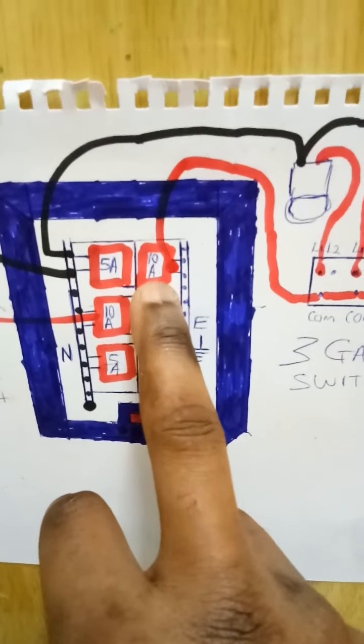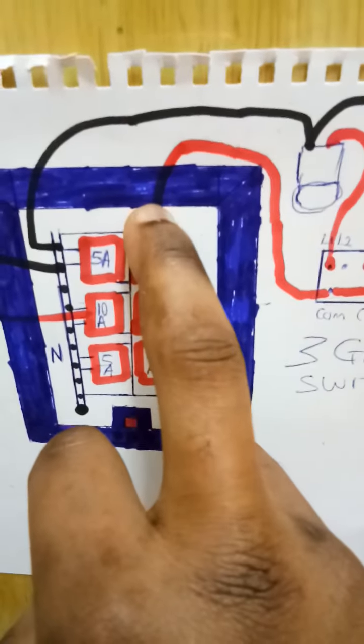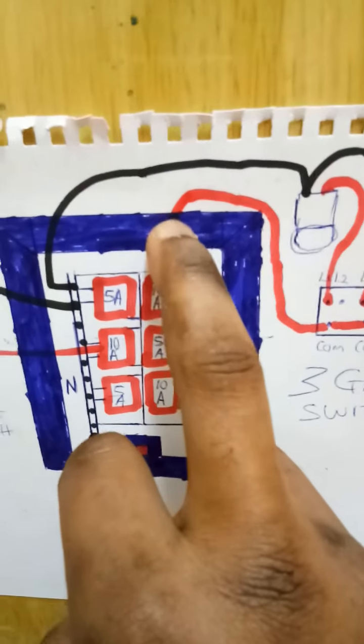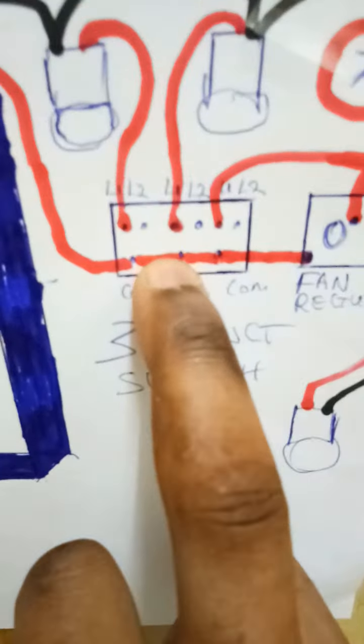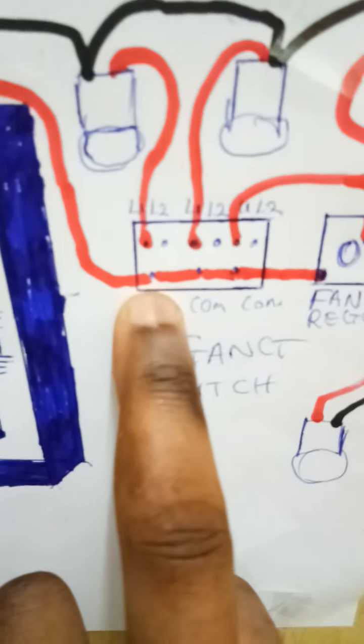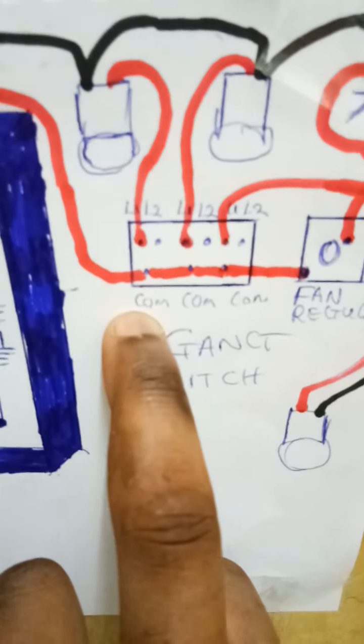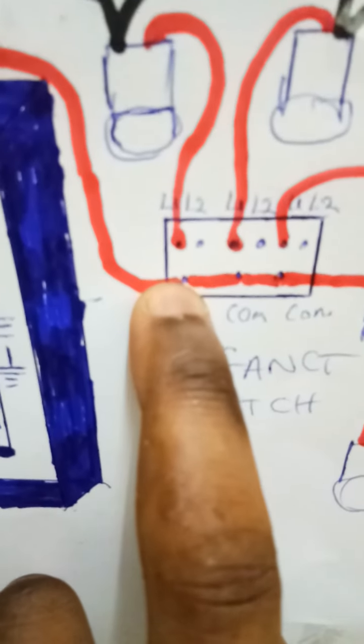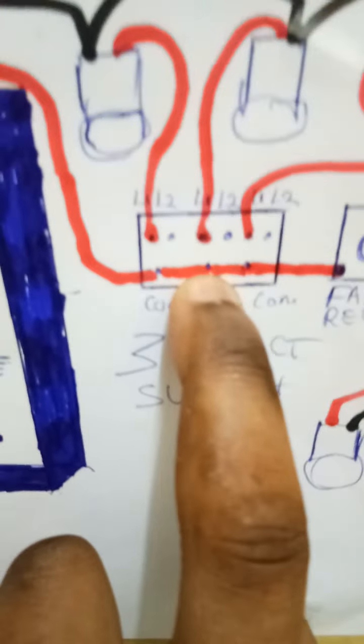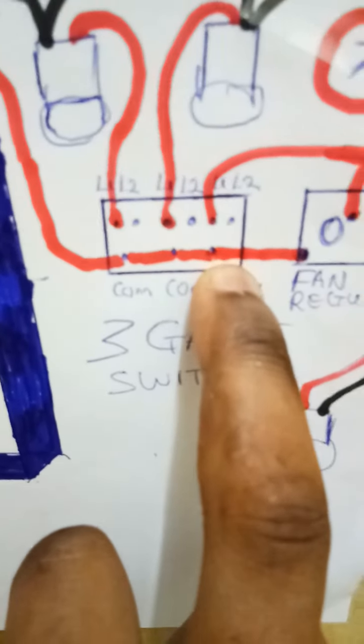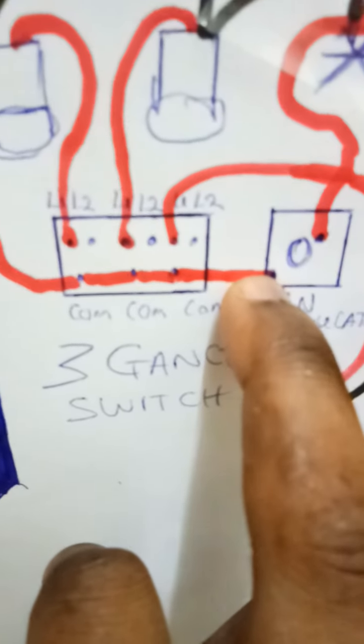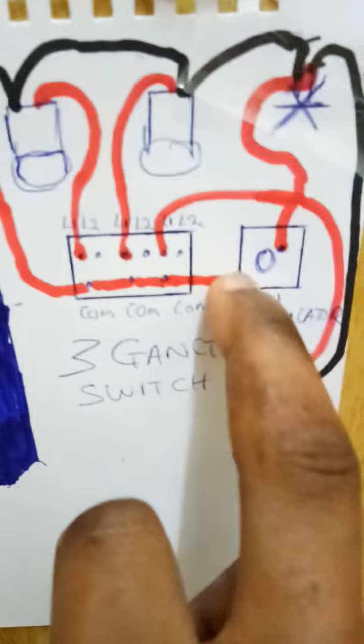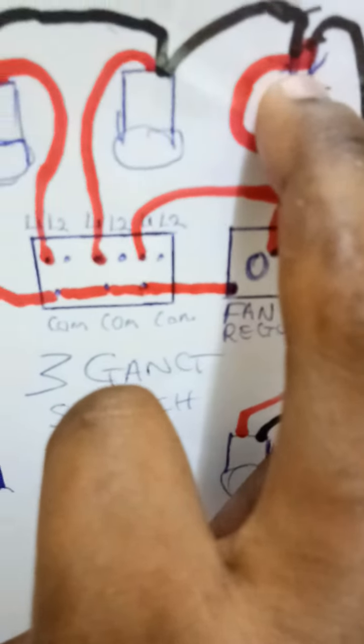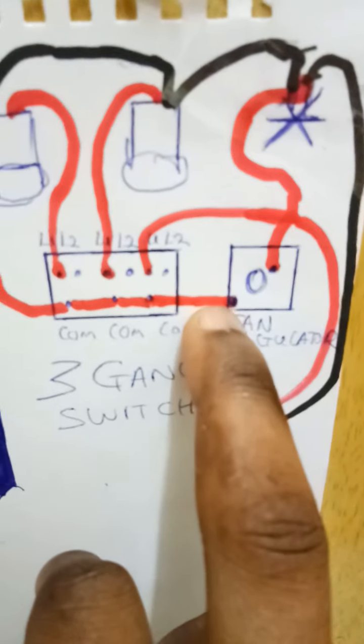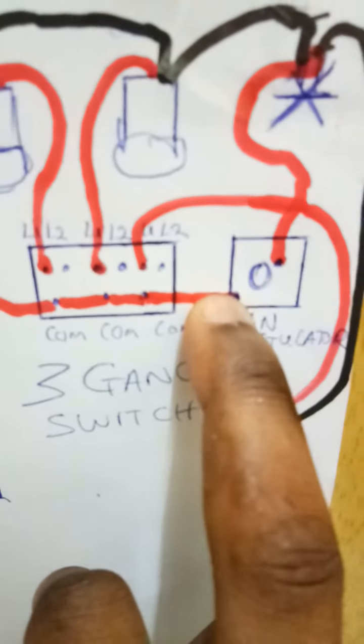As you can see from this 10 amp circuit, you see a red wire, 1.5 mm wire, going to a 3-gang switch. This switch, this is the common. It goes to one common. From one common, it is linked to the other common. From the second common, it is linked to the third common. From the third common, it is linked to the fan regulator. This here is a ceiling fan. From the common of the switch, it links to the fan regulator.